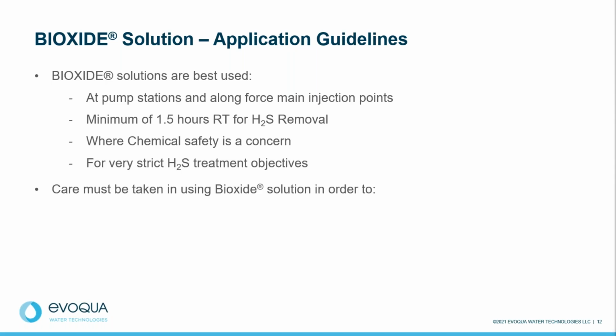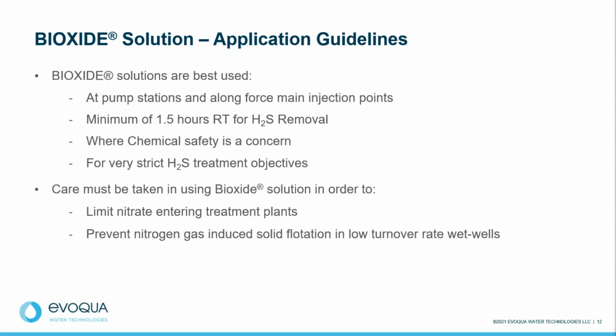We practice really good care in feeding BIOXIDE into our wastewater streams to limit the nitrate entering the treatment plants, to prevent nitrogen gas-induced solid flotation, or in other words, matting on these low flow rate wet wells. We also avoid large nitrogen gas buildups in certain types of force mains. Good care is taken to address all these issues.